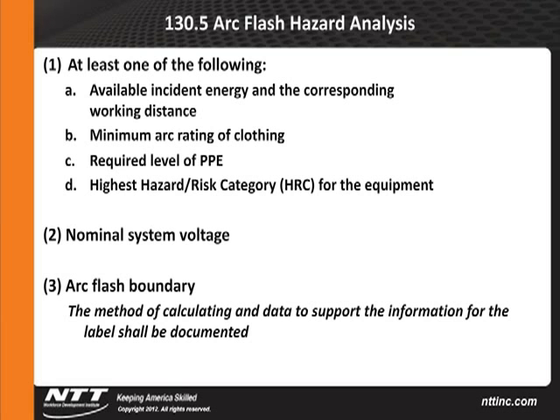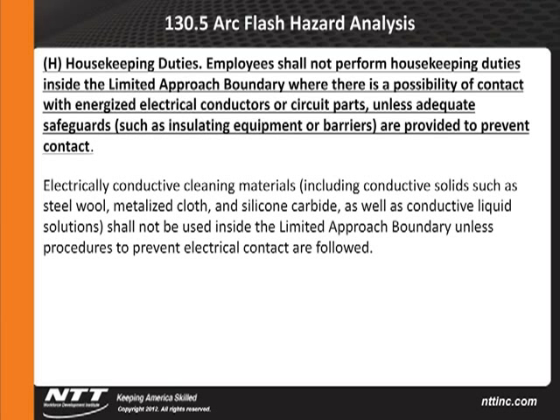Housekeeping duties. Employees shall not perform housekeeping duties inside the limited approach boundary where there's a possibility of contact with energized electrical conductors and circuit parts unless adequate safeguards such as insulating equipment or barriers are provided to prevent contact. This is helping clarify that when we've got somebody going into the electrical room and working around electrical equipment, can they clean it? Do they have to be trained?